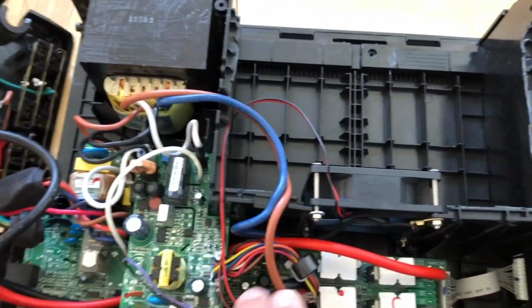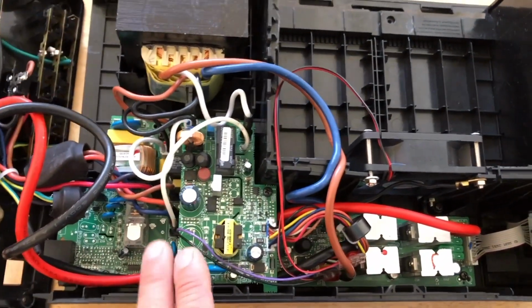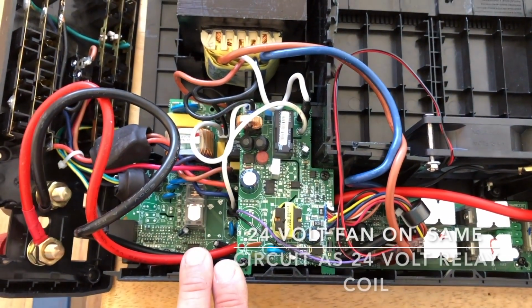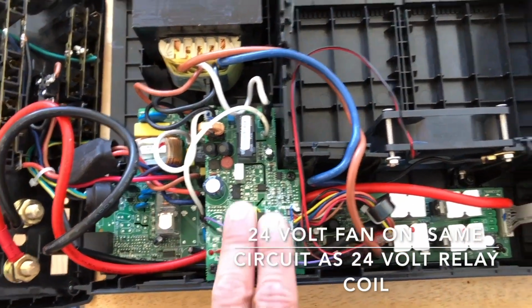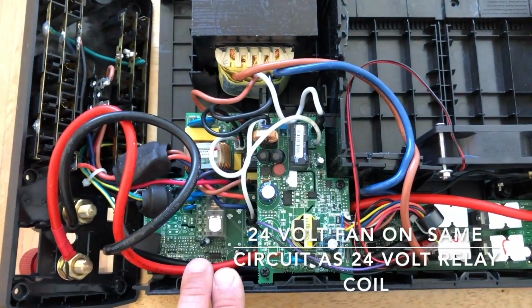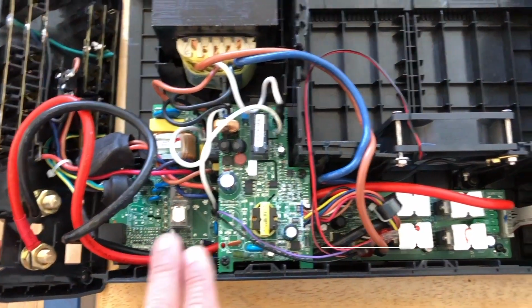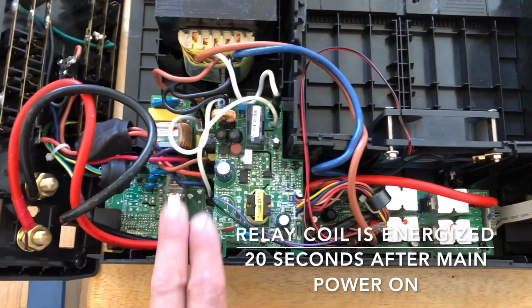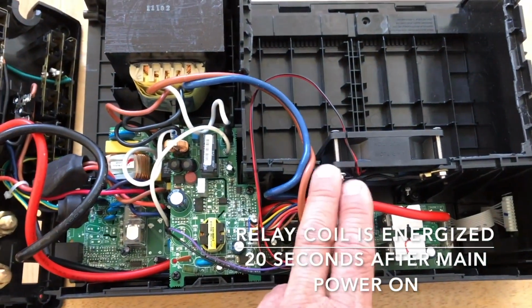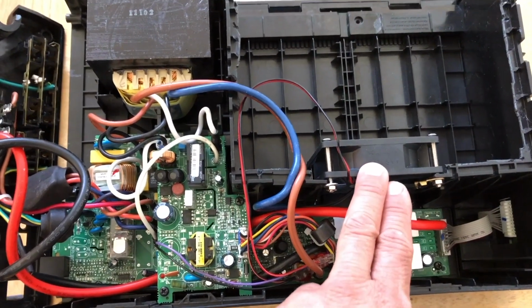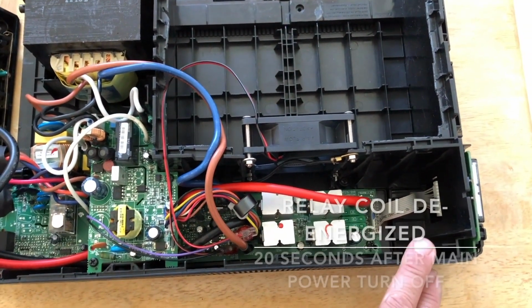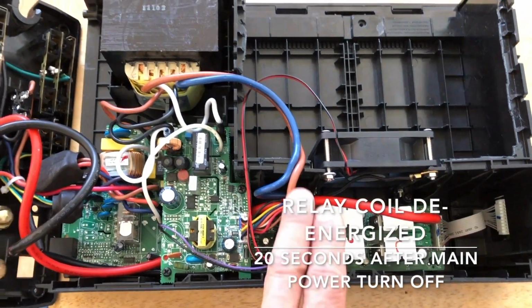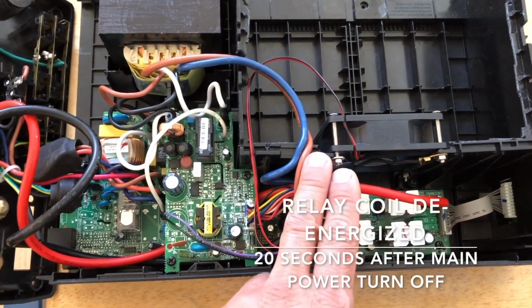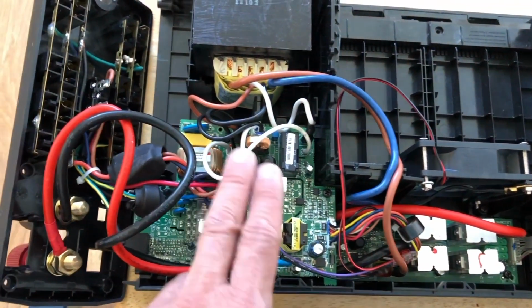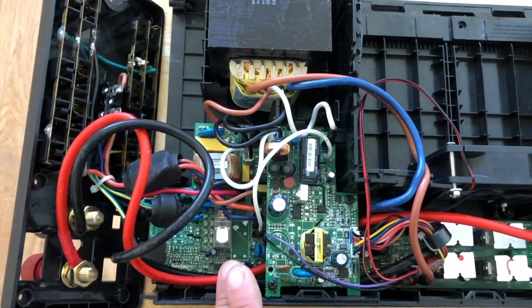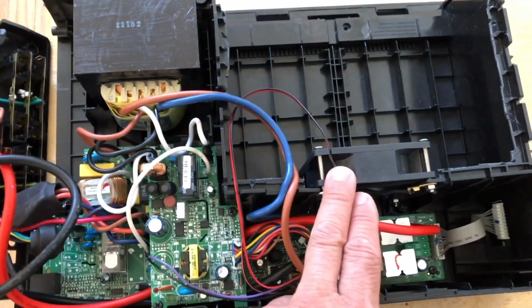And I don't know if you noticed, but you see the cooling fan is attached to the circuit board also. There is a relay that gets energized when it's running off the 24-volt battery power. When that relay coil is energized, that same power connection for the relay coil powers up the fan. So whenever the relay clicks after turning it on, for about maybe 15-20 seconds, it powers on the fan. And also when you shut off the unit, when you hit the power switch and turn it off, the fan runs for about another 15-20 seconds more, cooling it down. Then eventually a timeout circuit de-energizes the relay coil, which also cuts power to the fan.